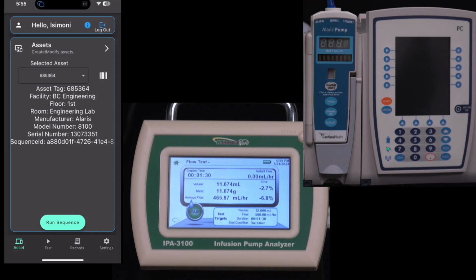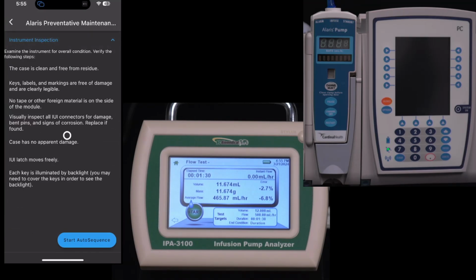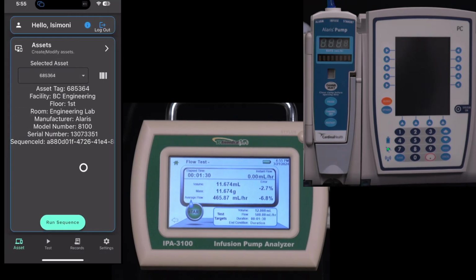I'd love to know about the IPA 3400. How can we test 4 at the same time? How would that process work, and does that save us a lot of time to do 4 at the same time? Well, it's really a matter of if you can keep up. You get all the administration sets loaded, and if you transfer those from pump to pump, then yeah, that can work really well. It's very similar to this auto sequence that we had on the 3100. You can set up checklists. You can set up all of those tests on the 3400, and 4 channels can be running independently on 4 different pumps. So that's a great question.